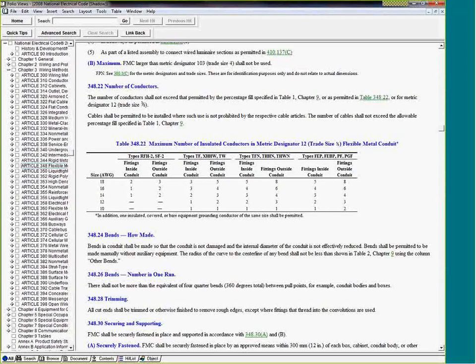Yes, we are dealing with Liquidtight, but it refers us directly to flexible. So here's my THHN, my number 12. Can you see number 12 right here? It says fittings outside, fittings inside. Remember, it always says fittings outside. If it's Liquidtight, all fittings are outside. And that's my insulation, THHN. So how many conductors can fit in this 3/4 inch Liquidtight conduit? I can fit only 3. I don't want you to get confused by the top saying flexible metal conduit. It refers you to that table from the Liquidtight article, so don't worry about that. So that's the 3 of them.